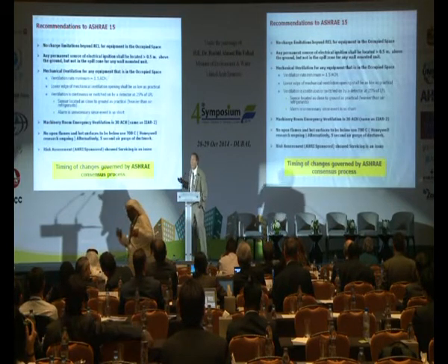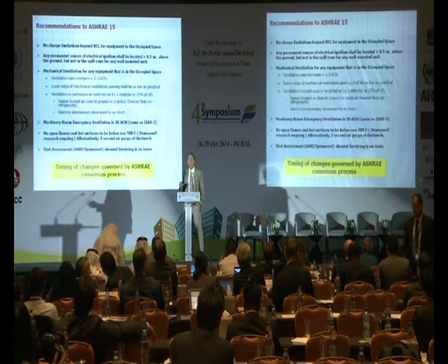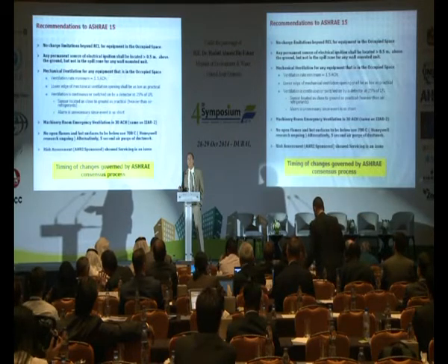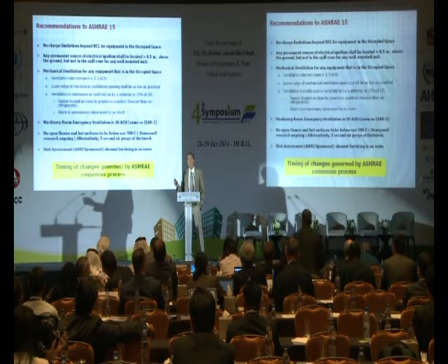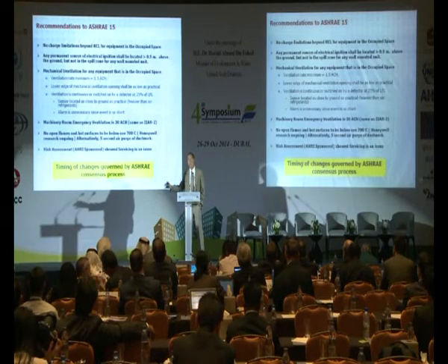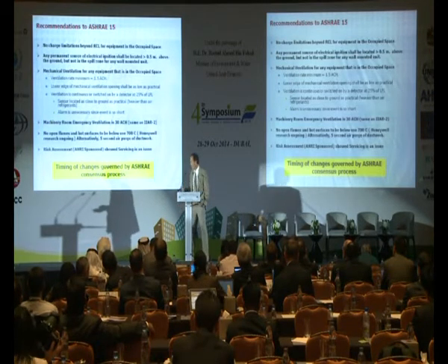I showed you the various spill zones. We want to make sure that any electrical sources, the most likely source of ignition, are located well away from those spill zones. So we want those ignition sources to be above a half a meter in a room, or we want them to be outside of the spill zone for anything that's located on a wall. Inherent safety if you move those potential ignition sources away from the spill zone.